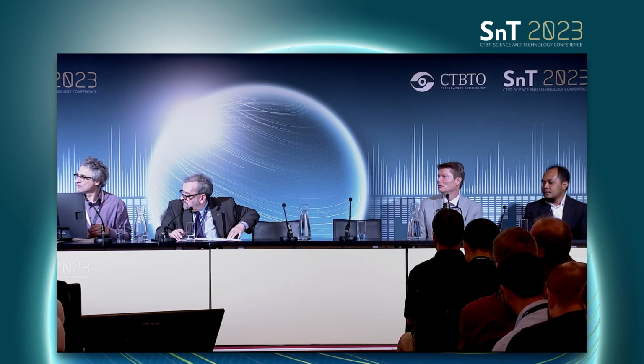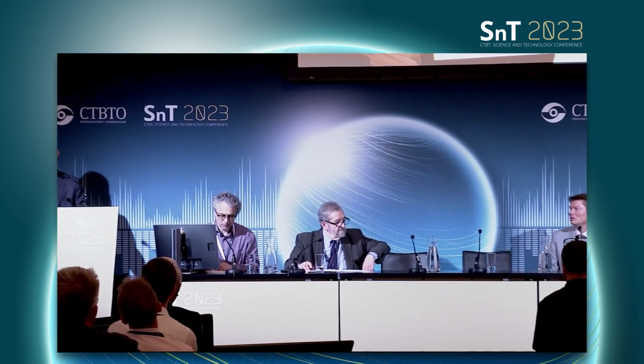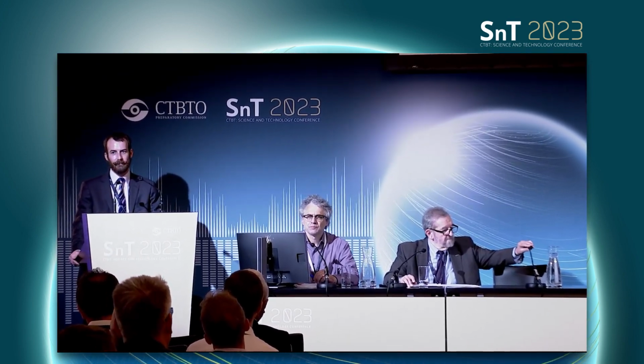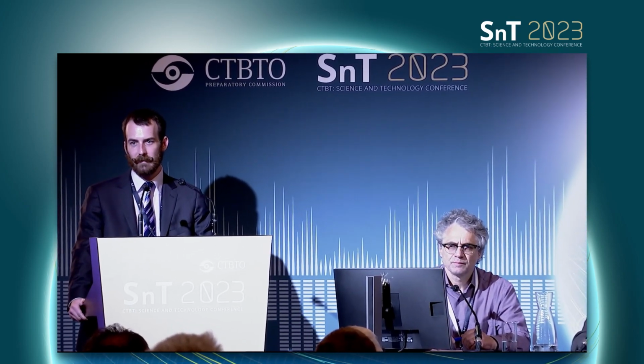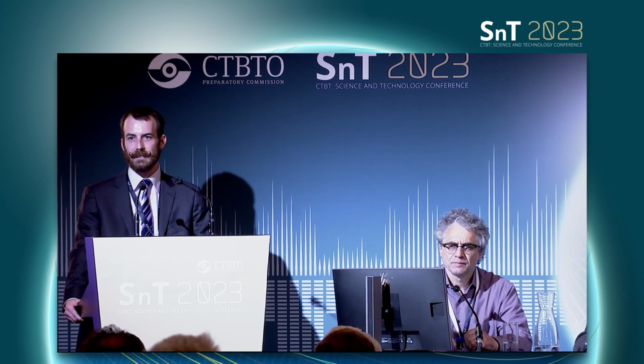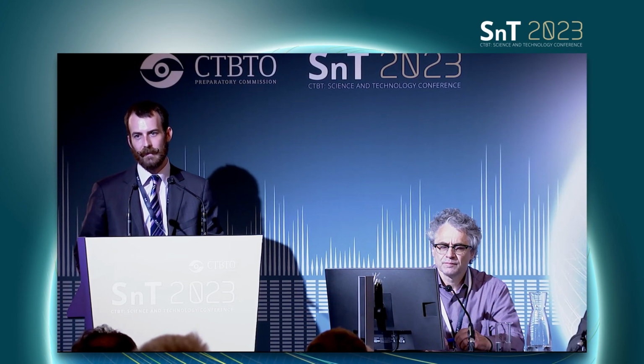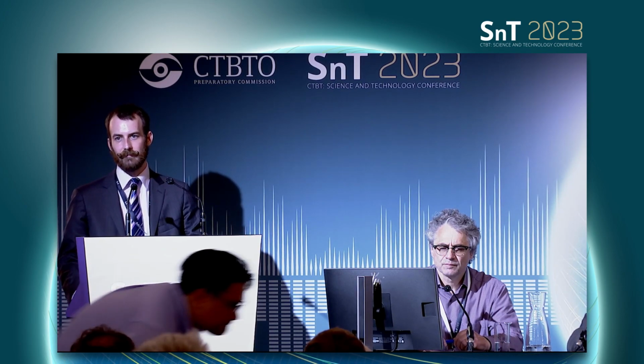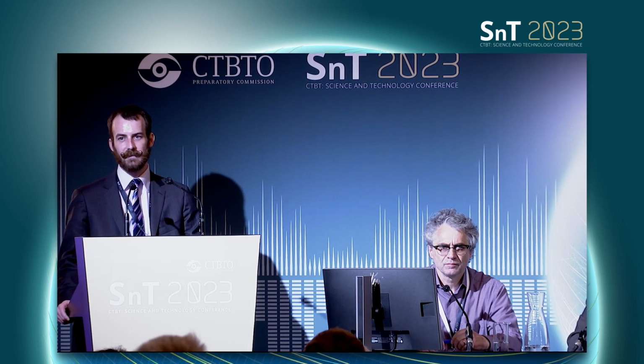So right now for USL16, we use the standard 24-hour measurement time, which works well for the 133 and 131m on average. But I think as we move forward, there's potential if we want to try to target a different duration. But there are studies that I think need to also be done to understand what's the rate of the gas loss from a cell potentially, or what's the impact of the longer measurement duration, so that we can certify those with the PTS as well.